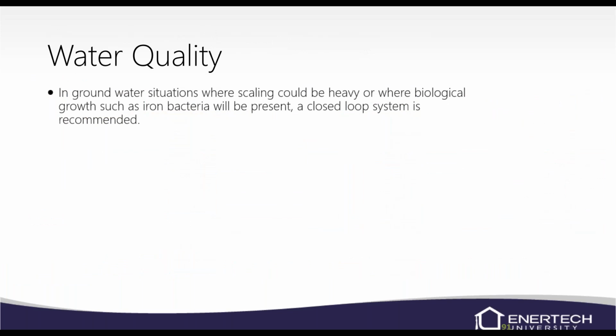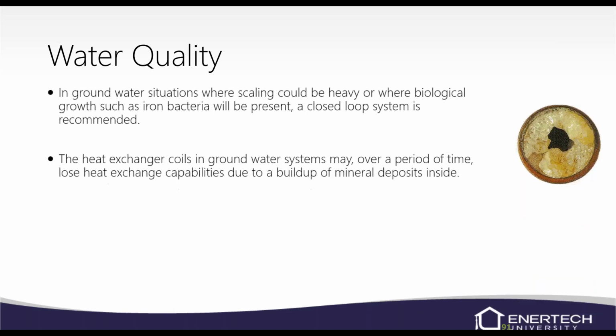If you have bad water quality, don't use the open loop. If you've got bad water quality, don't use it on a closed loop either. Bring your water in from somewhere else. Just because it comes out of the tap does not mean it's good. So just be careful with your water. Always check it. Always, always, always.